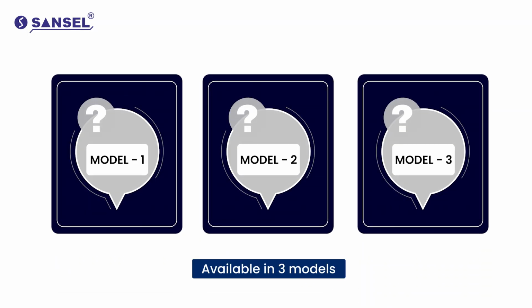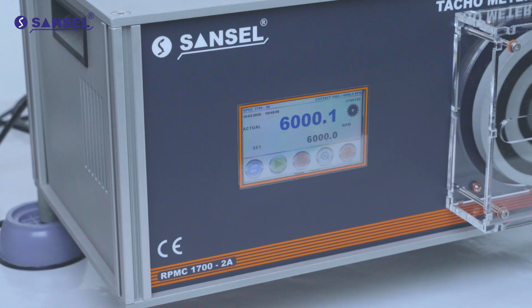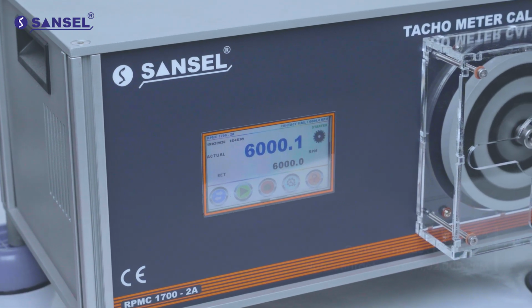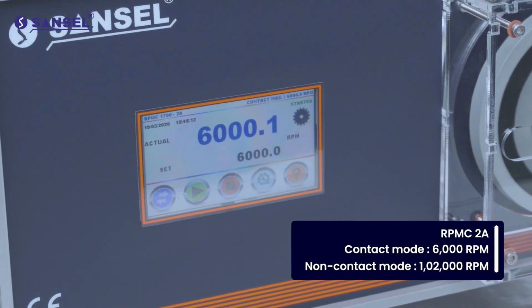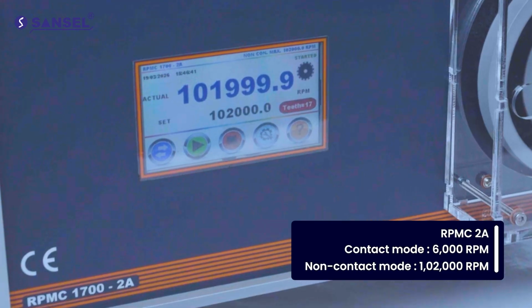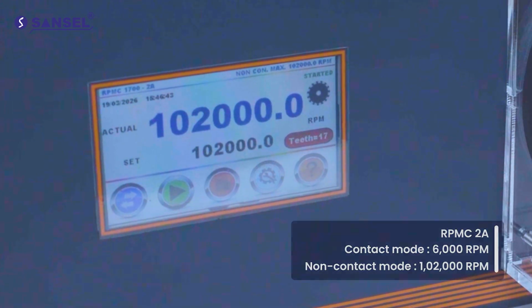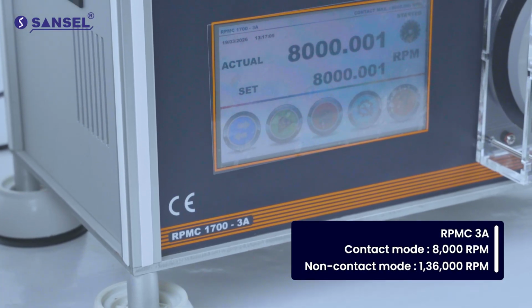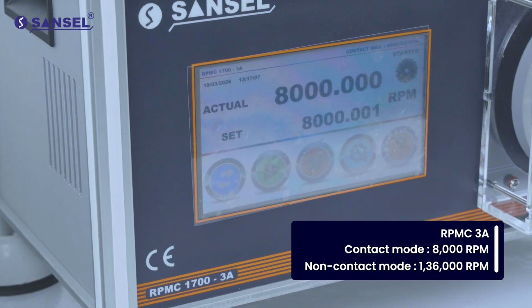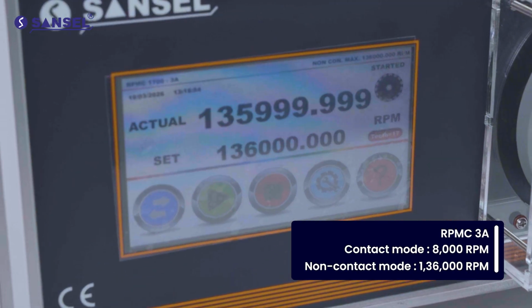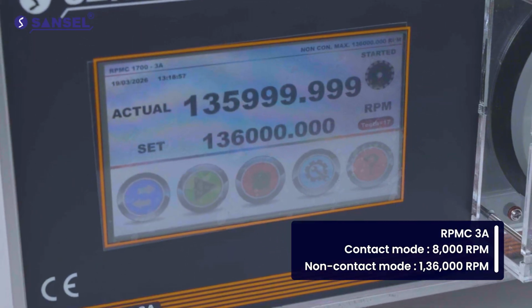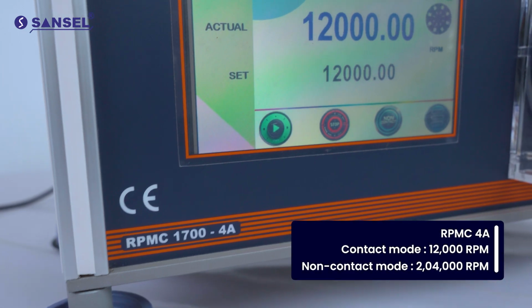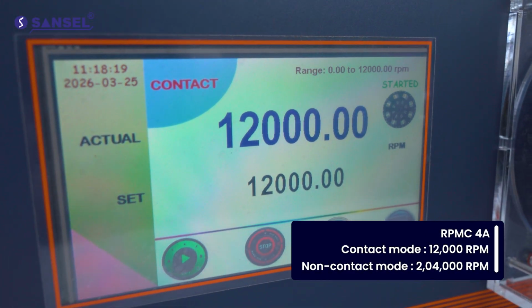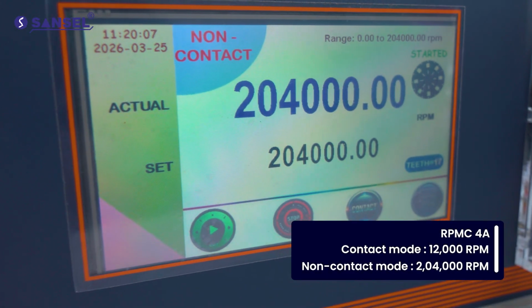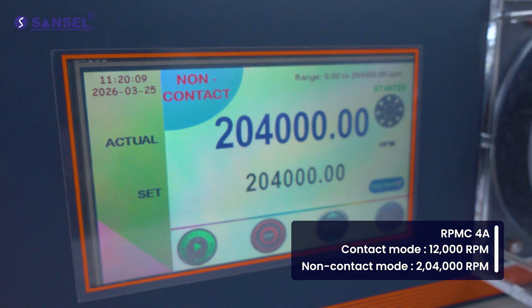Available in 3 models. RPMC 2A with a set range up to 6000 RPM in contact mode and 1,02,000 RPM in non-contact mode. The 3A model offers up to 8000 RPM in contact and 1,36,000 RPM in non-contact. The 4A model offers up to 12,000 RPM in contact and 2,04,000 RPM in non-contact mode.